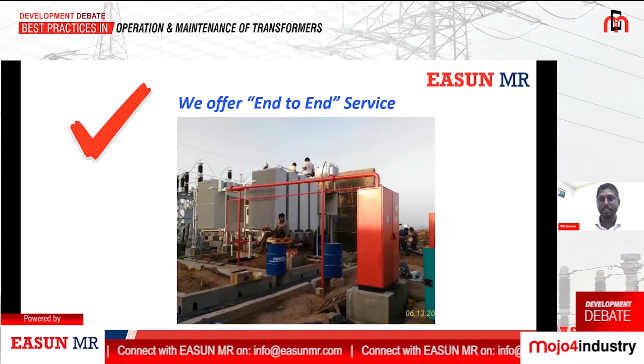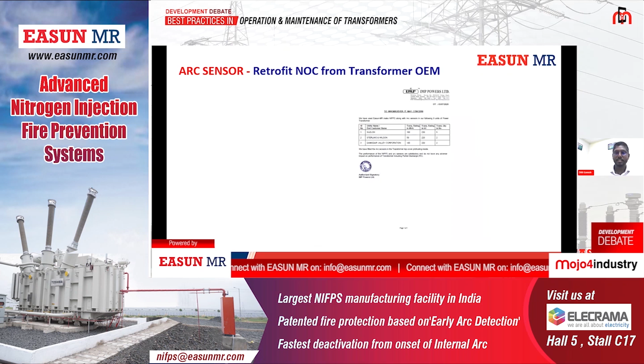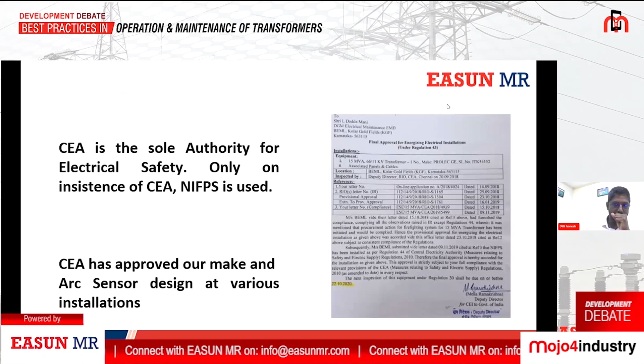We do not make you go through trouble. If you are coming with us, we offer an end-to-end solution. We have an entire setup for that. We have almost 28 different teams, different crews, working on it. We have taken an NOC from almost all the transformer manufacturing companies in India. Fitting the arc sensor does not affect the performance of the transformer. We are approved by almost all the Indian state utilities, NTPC, PGCIL, and the central ones. CEA is the sole authority for electrical safety, and they have also approved our arc sensor based technology to be installed in transformers.